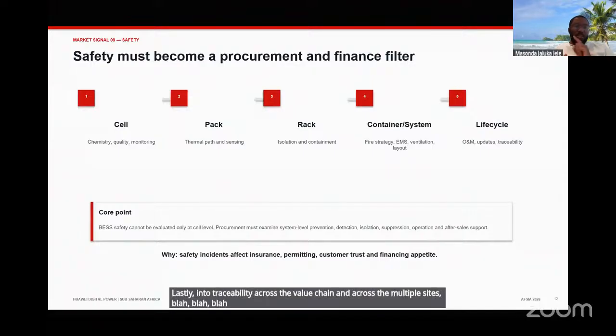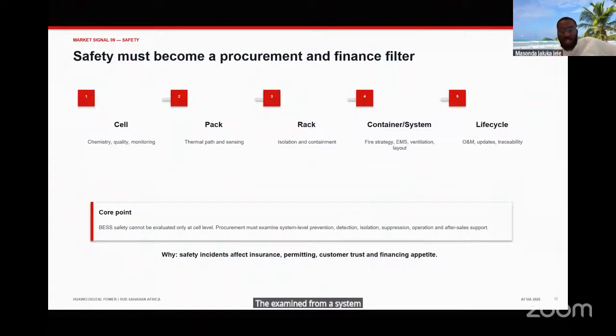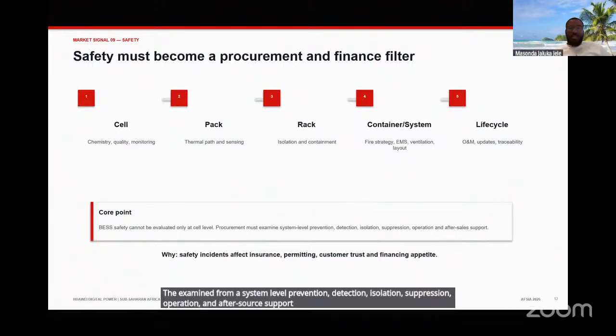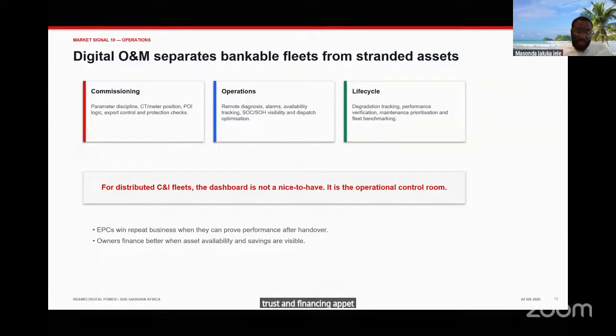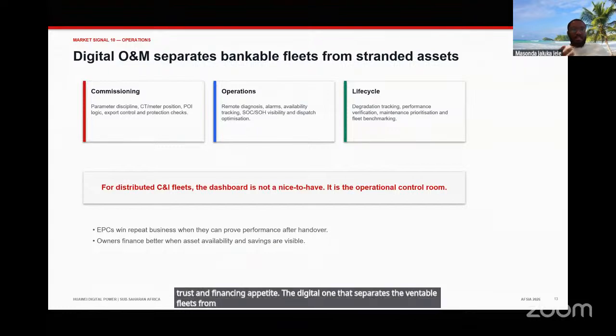The core point is that when it comes to BESS, safety cannot be evaluated only at a cell level. Procurement must be examined from a system level: prevention, detection, isolation, suppression, operation, and after-sales support. Safety incidents affect insurance, permitting, customer trust, and financing appetite. The digital O&M is what separates the bankable fleets from the stranded assets from an operational standpoint. You have your commissioning, you have operations, and lastly, there's life cycle.